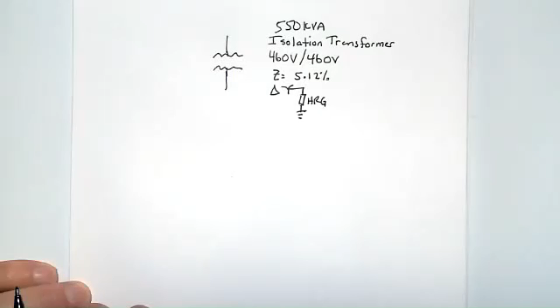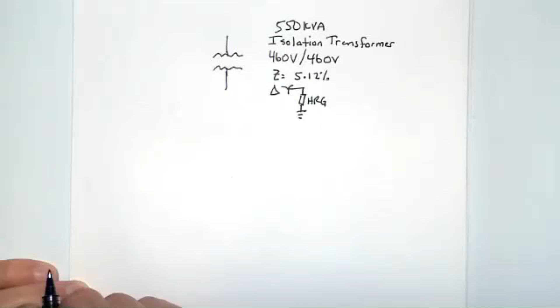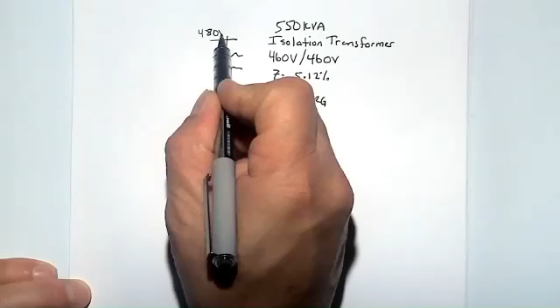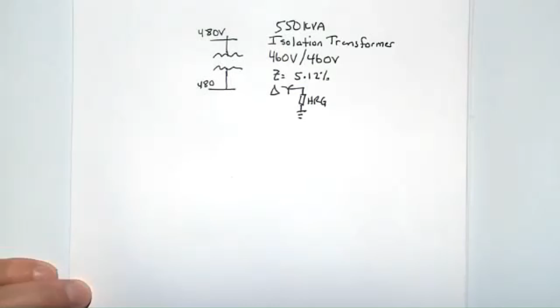Okay, for the next transformer, we have this unique isolation transformer. And again, it's 550 kVA, 460 volt rated in, 460 volt rated out, 5.12% impedance. Now, we're probably going to apply this on a 480 volt system. So the bus voltage here is 480 volt, and the bus voltage here is 480 volt line to line. But how are we going to calculate the full load amps on the primary and secondary and calculate our fault current?